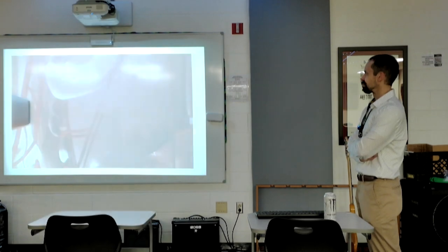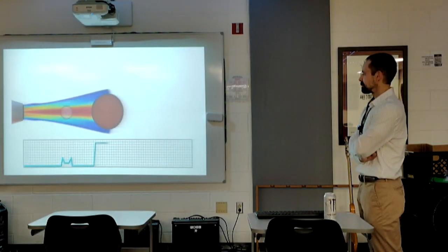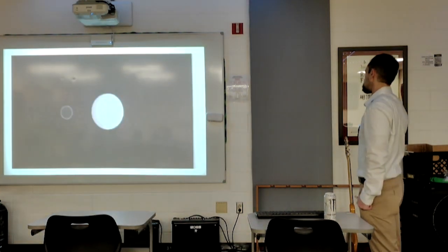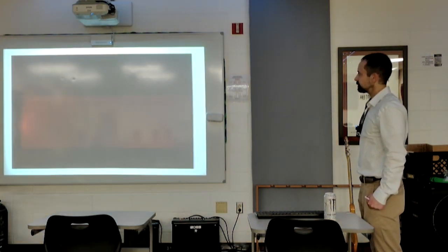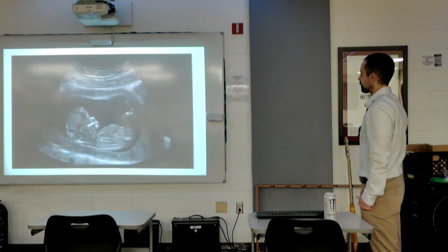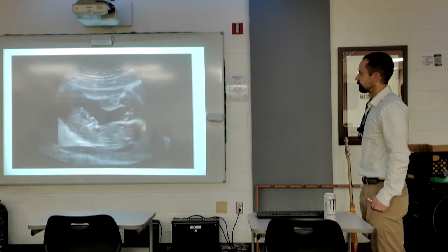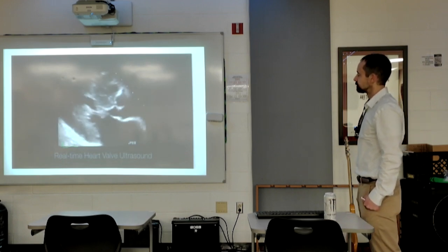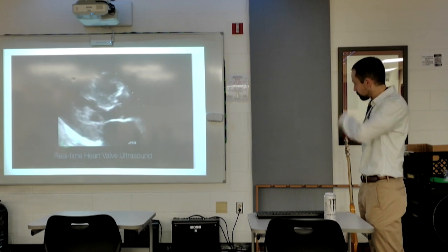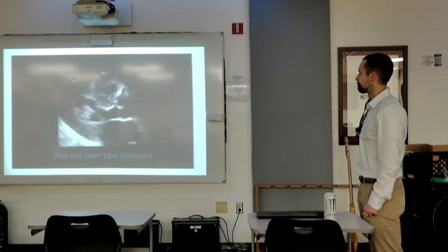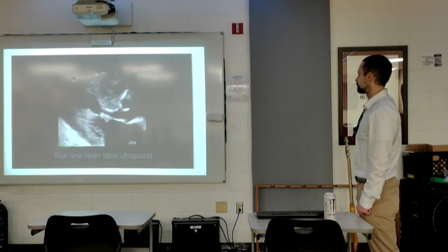This happens more than 1,000 times a second. Returning echoes are converted to electric signals, which a computer converts into points of brightness on the image, corresponding to the anatomic position and the strength of the reflected echoes. A medical transducer contains a large array of crystals, which allow it to make a series of image lines that, together, form a complete image frame, called a sonogram. In addition, all the crystals are repeatedly activated many times in such a way that a complete image frame is formed around 20 times per second, so that real-time motion is displayed in the ultrasound image.